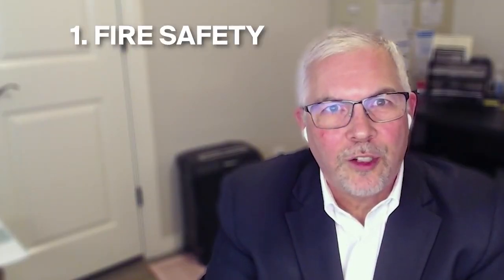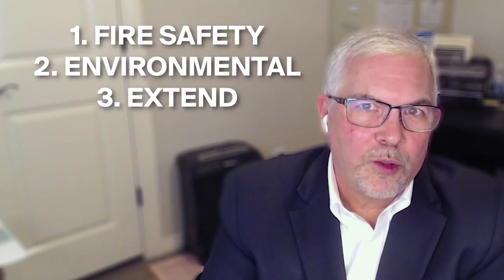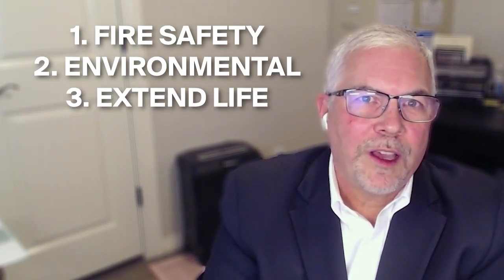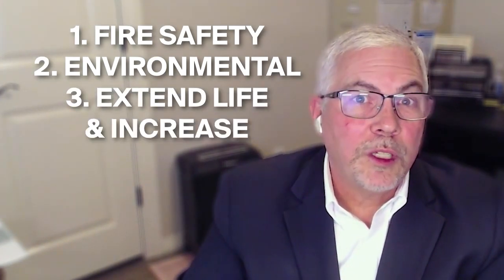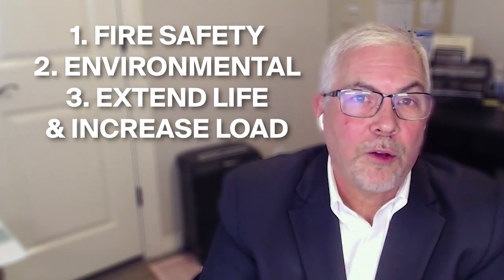But when we look at using FR3, we look at, again, the three main reasons, the motivators, if you will. One is the fire safety, second is the environmental issues, and the third is the ability to either extend the life of the transformer or take advantage of the opportunity to increase load on the same footprint, basically increase the power density. And I have found that is more important to people than extending the life of the transformer. They're more interested in, just because space is always a constraint, trying to get as much power through that transformer as possible.